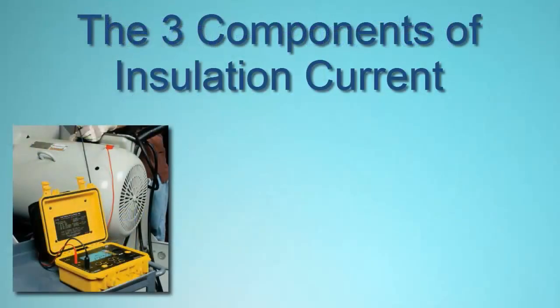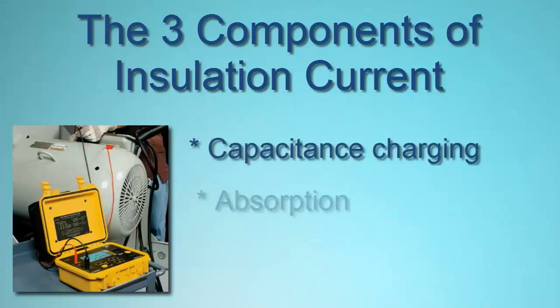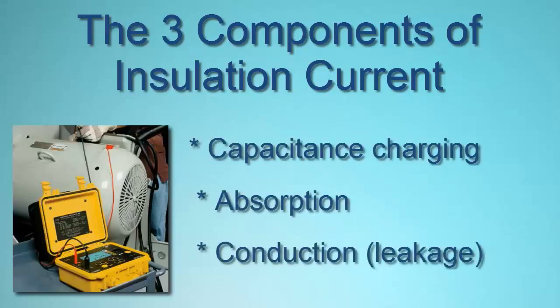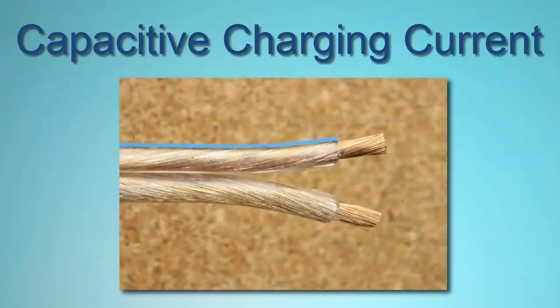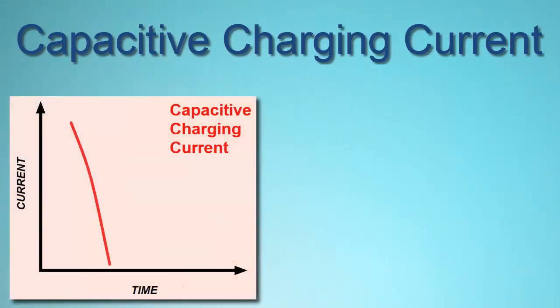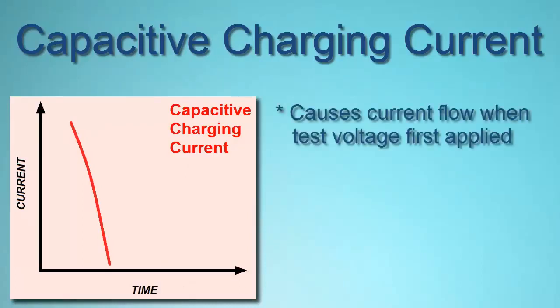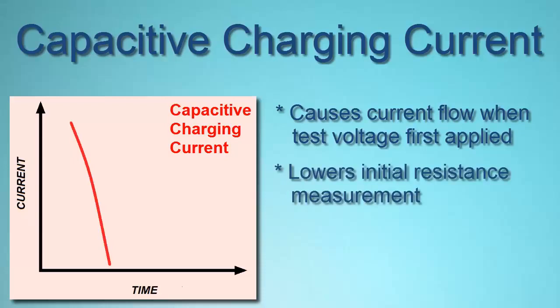To properly interpret test results, it's important to understand that the total current flowing through the insulation consists of three components: capacitive charging current, absorption current, and conduction or leakage current. When two conductors are in close proximity separated by an insulator, they can act as a capacitor. When test voltage is first applied, this capacitive charging effect results in current briefly flowing through the conductors until the voltage across the insulation reaches the test voltage. Consequently, the initial resistance measurement would be relatively low and then quickly rise as the capacitance becomes fully charged.